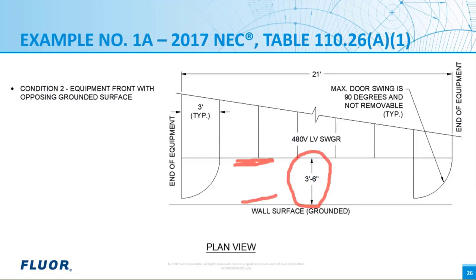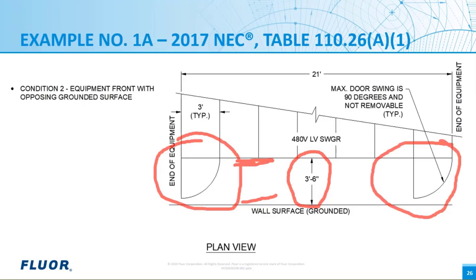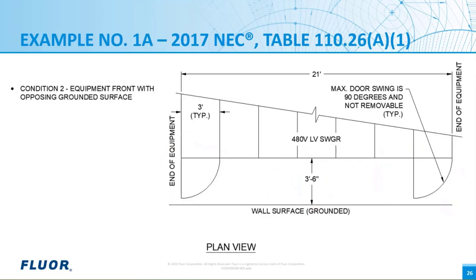The main point here is if the doors to the equipment are open, the entrance and egress from the working space is actually blocked. So if there was a fault or a fire in the equipment, then the electrical worker escape path could be blocked by an open door. I want to point out in the first couple of examples today, we're going to be standardizing on large 480 volt equipment that is 36 inches wide, that has 36 inch doors that open only 90 degrees, and the doors are not removable. Note that all the equipment lengths in these examples will be longer than 6 feet.